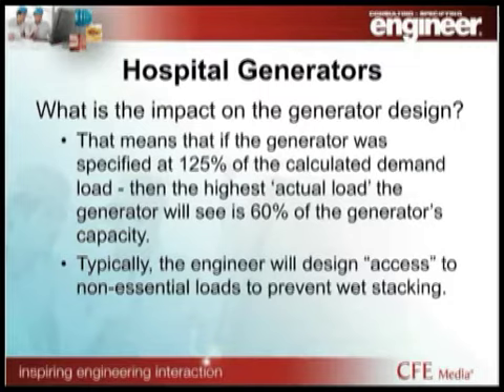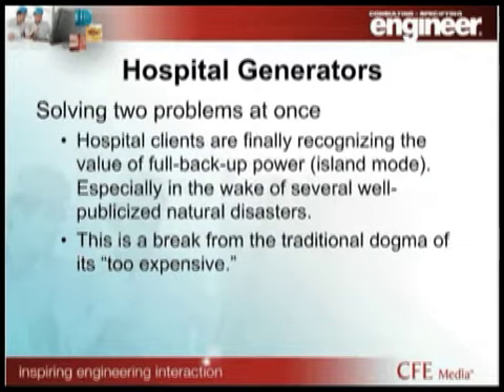And then the other thing is give access to the emergency board from your normal loads. This has become real commonplace, to actually give a manual process to your facilities engineer. Kirk Key interlock might be a term that some of y'all are familiar with, to artificially load that generator whenever they test it, monthly or annually. So that solves two problems at once. One, once you make that manual connection between the emergency board and the normal board, you are giving the client access to full backup power.